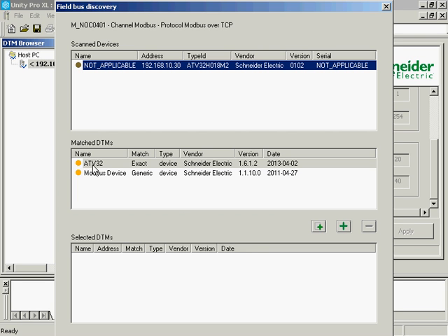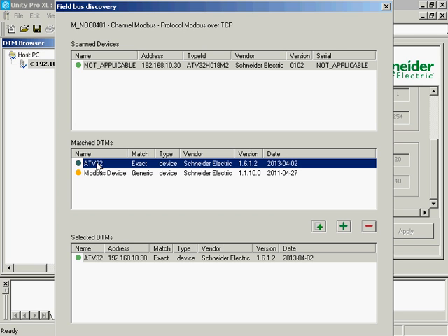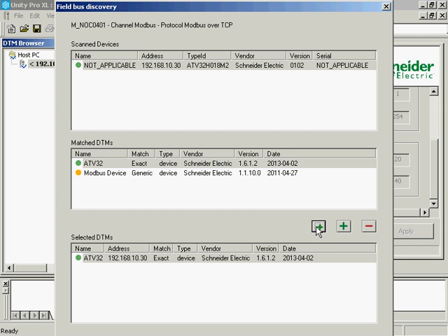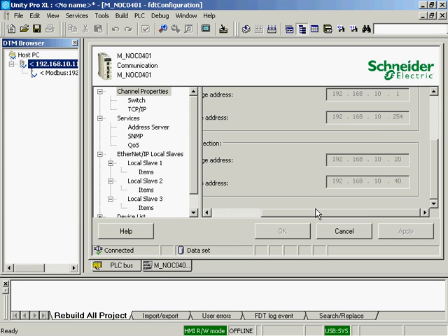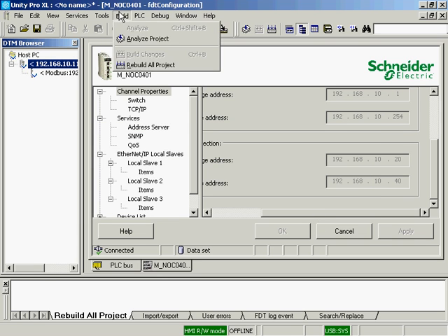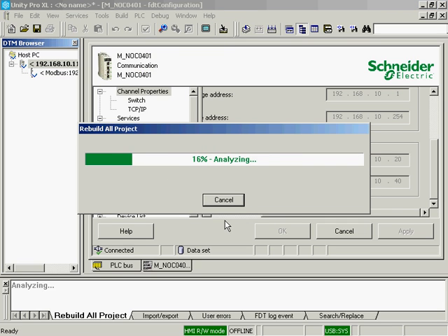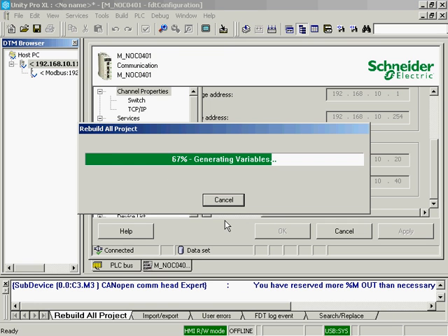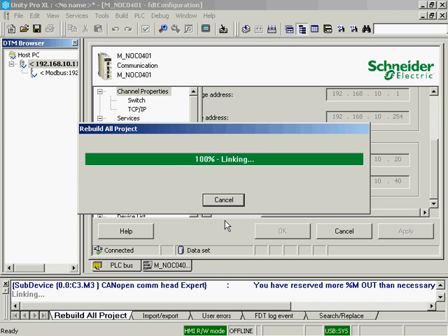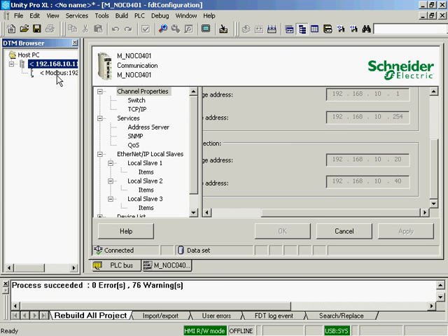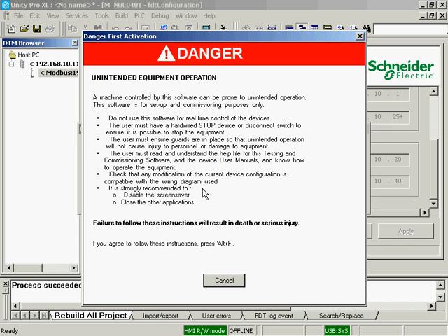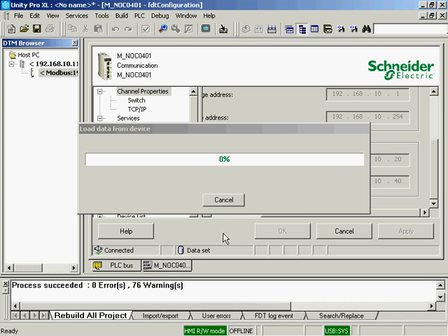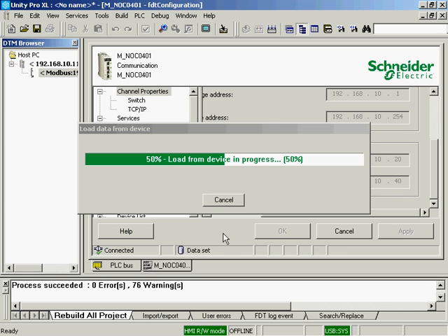It's going to go out and look for all the devices between 20 and 40 on our IP, and discover that I have an exact match of an ATV32. I'm going to double-click it so that I've selected that. And I'll OK this. At this point, I like to rebuild all the project. I will right-click the ATV32, and I will load the data from the device itself. We'll load all the parameters from the drive.